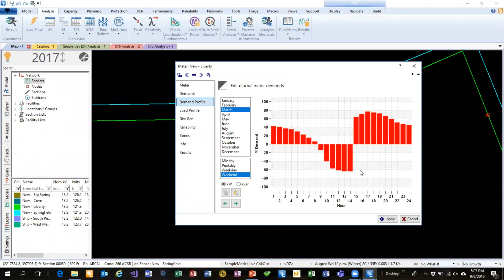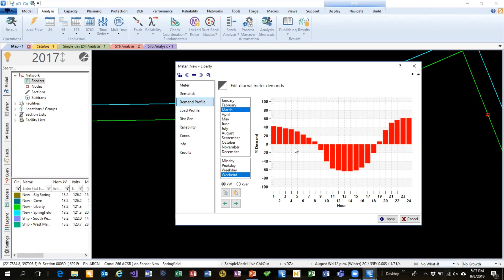When you pull that data into Synergi, this load profile is a copy of that data. There are tools in Synergi to massage this load profile. Why would you want to do that? Well, my demand on my feeder, if I have a bunch of PV, if I've got a feeder with high PV penetration, it may look like this. And this is certainly not the way that my loads are going to operate on that feeder. So we need some way to take this data and generate a load profile.